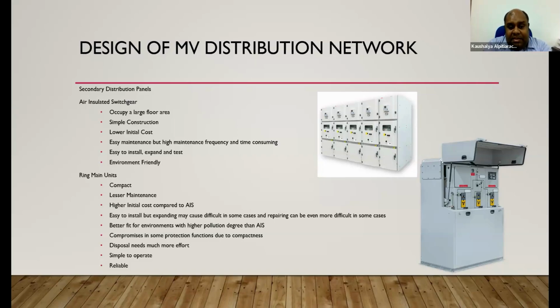Better fit for environments with a higher pollution degree than AIS. Yes, because the RMU has a sealed switching chamber, or sometimes the breaker chamber or busbar chamber, because of the SF6 gas. So ingress of foreign objects is completely prevented. Therefore, for harsh environments, this will be more suitable than an AIS. AIS also can be used, but will have much higher frequency of maintenance rounds.